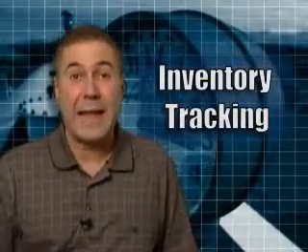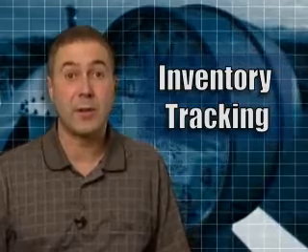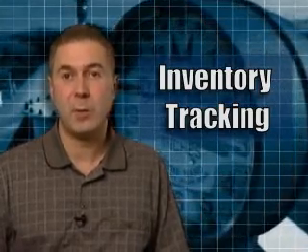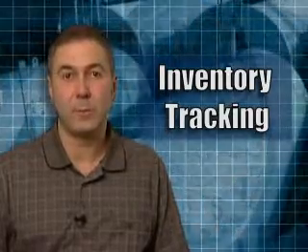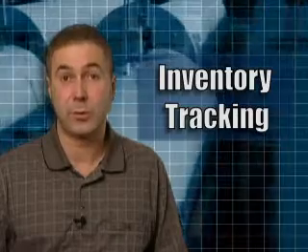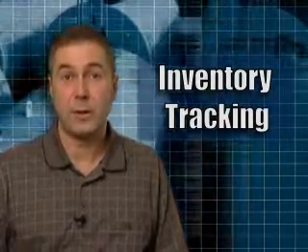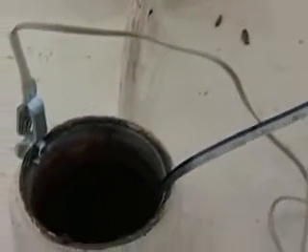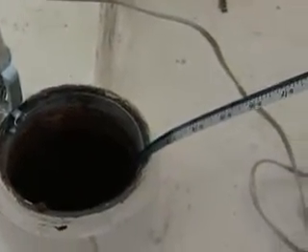At a busy gas station in a city, this is typically done on a daily basis. For a normal, smaller village facility, we would recommend that it be done at least once a month. It should be done more often during periods of high use, such as during hunting season. It's also a good idea to check your inventory immediately before and immediately after a delivery so you can see that you got the fuel that you paid for.